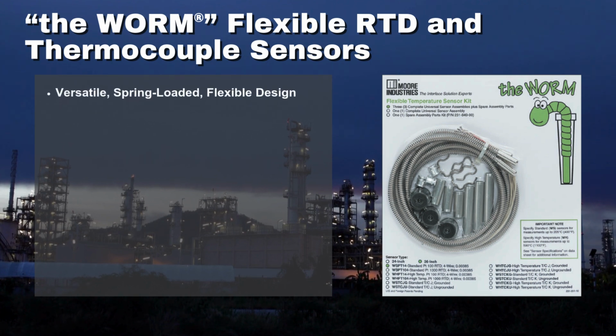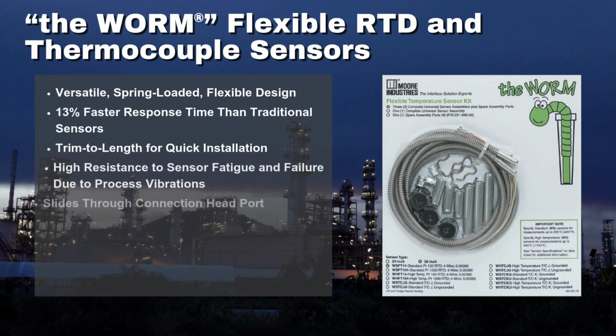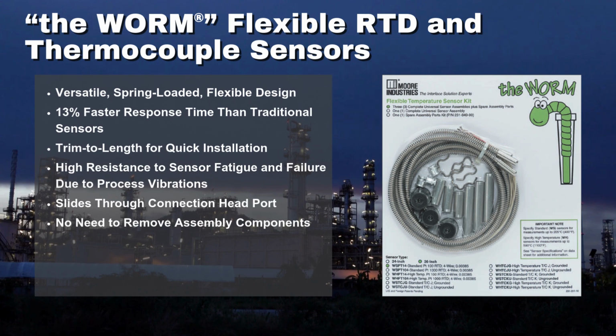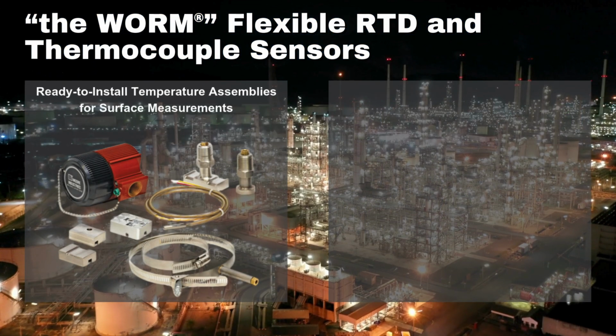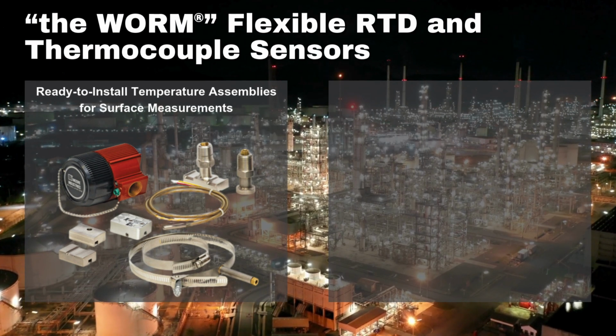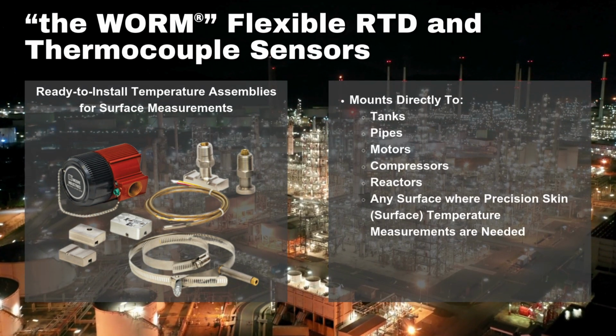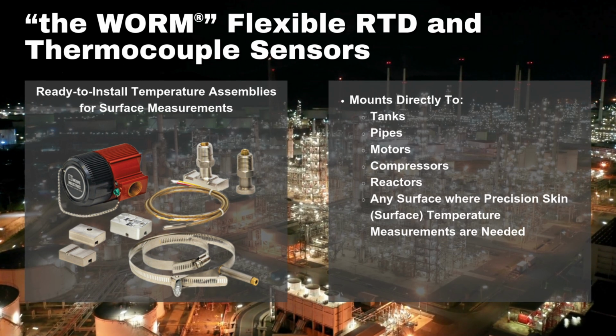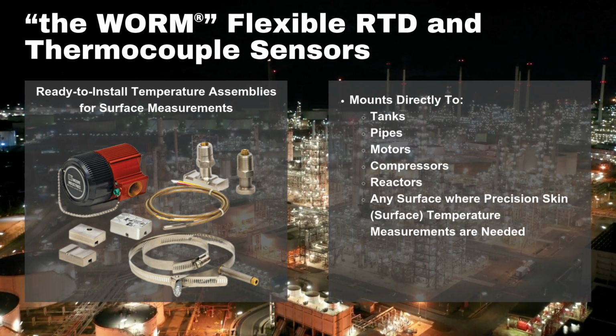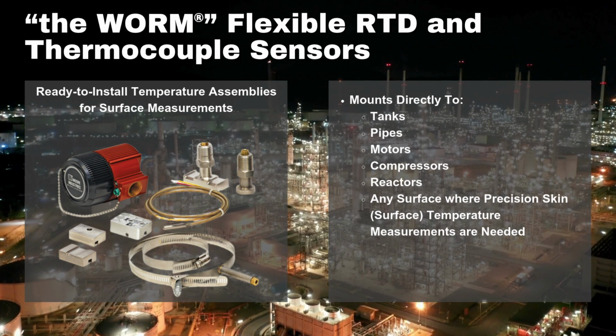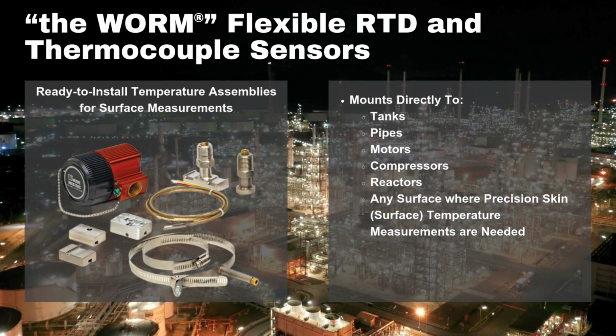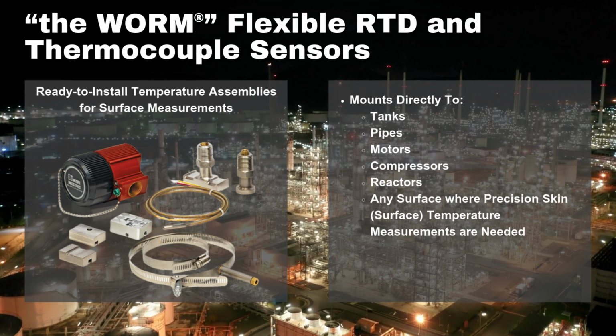This versatile, spring-loaded, and flexible sensor trims to length for quick and easy installation. Unlike conventional solid sheath sensors, the worm's flexible design allows it to slide easily through the connection head port and into the assembly. No need to remove assembly components. Our temperature assemblies featuring the worm are perfect for surface measurements. These assemblies mount directly to tanks, pipes, motors, compressors, reactors, or any surface where precise skin temperature measurements are needed. With precise engineering and sturdy construction, these assemblies are designed to endure the harshest plant conditions and demanding field environments.